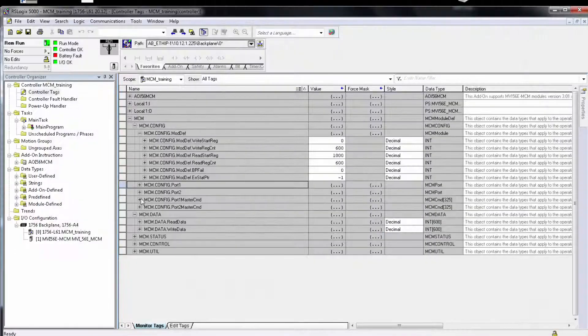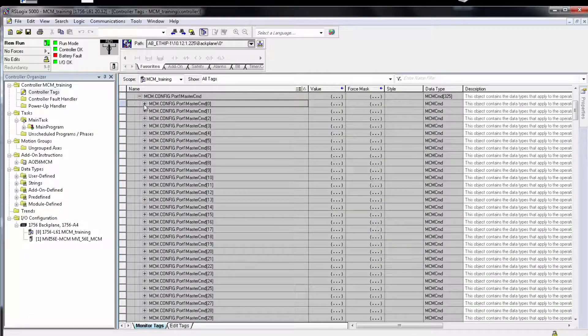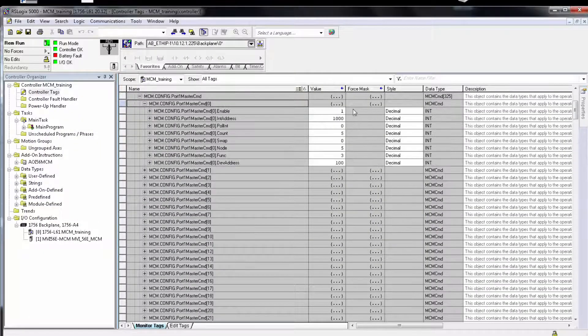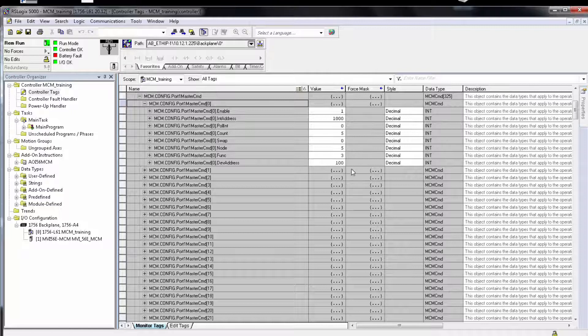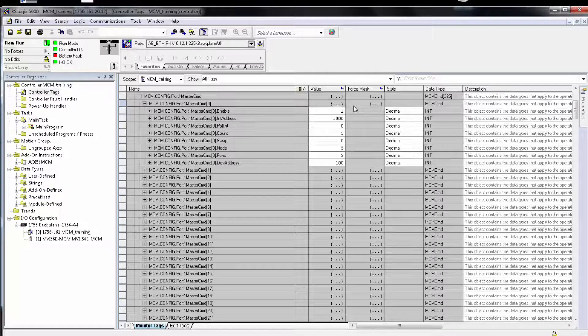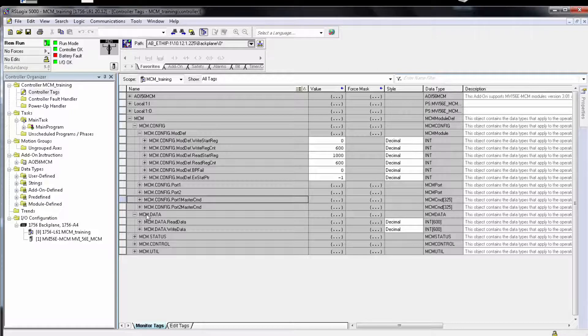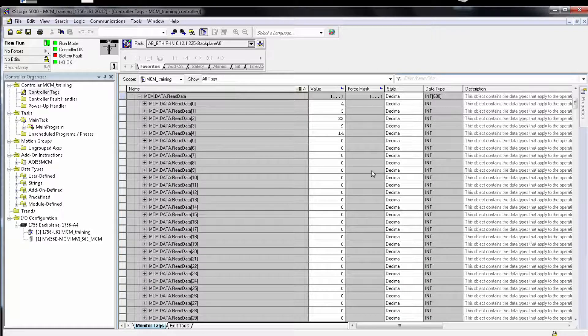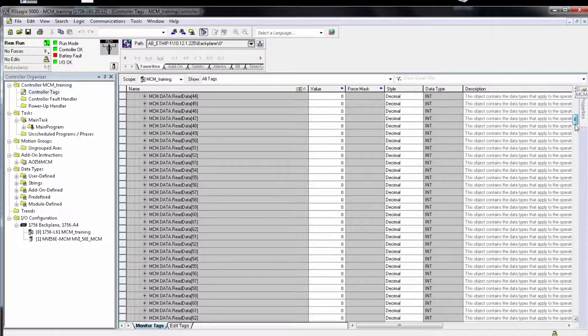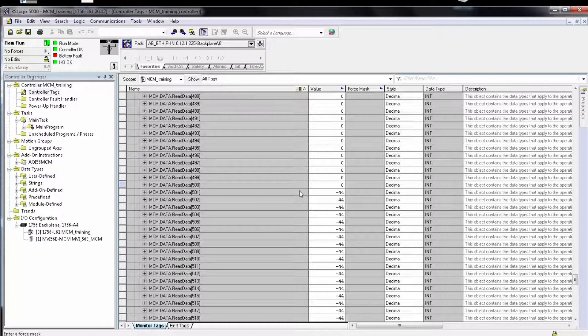Now let's take a look at the command error pointer in action. So I've already set up a command for the gateway to read data from a server device. My command error pointer is set to appear under my read data at address 500. The program is running and as you can see address 500 is showing a zero.